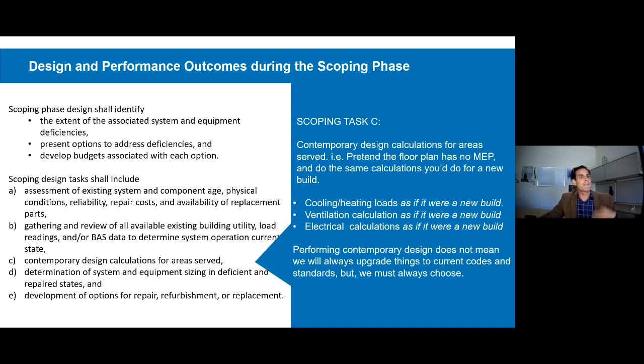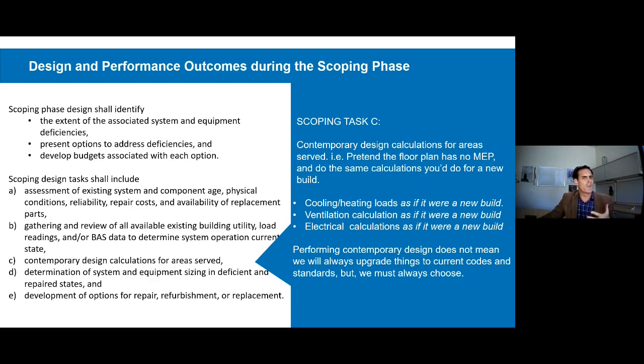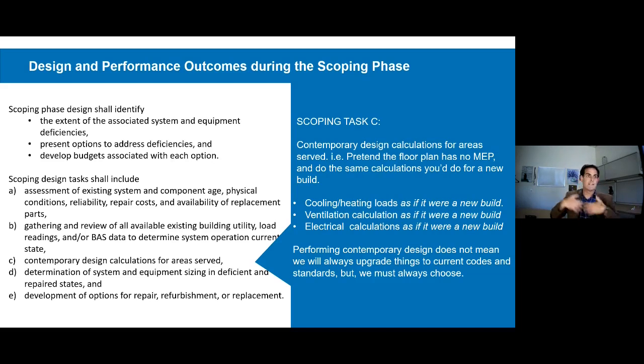The way to think about this is: we should not be assuming that the previous design engineer was correct. Someone drew the plans 10 or 15 years ago for the existing building, and we are not going to assume that all of their numbers for all the zones were correct and are still valid today. It may turn out that 80% of that work done in the past is okay, but we're going to actually validate that. In this step we would look at the architectural floor plans as if it was a new building and do cooling load calculations, heating load calculations, electrical calculations, and ventilation calculations as if it were a new building.